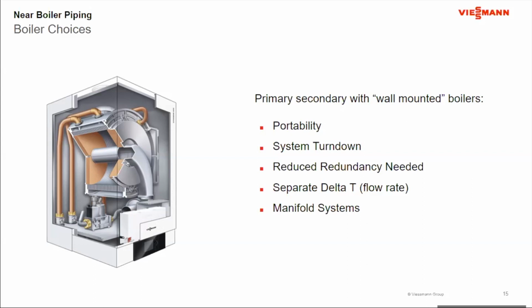The other big advantage of going with the smaller wall-hung boiler is system turn down. Typically when I look at wall-hung boilers, because I'm stopping at 5 million, I'm probably going to have 2, 3, or 4 to meet the load of the system. So now I have system turn down working in my favor. The other thing with wall-hung boilers is I typically end up with reduced redundancy needed. Even though the requirement's probably going to be n+1 on redundancy, if I do a building where the load of the building is 1 million BTUs, I do a 1 million BTU floor-standing boiler.